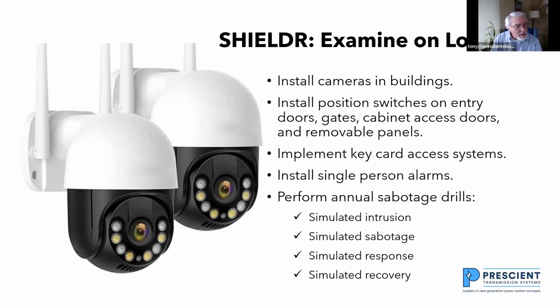And single person alarms, we shouldn't have single individuals able to access critical substations. What we should do is have it set up so that if 2 people aren't in a critical substation within 5 minutes of each other, security is alerted and security comes out to the site and asks a question. Why are you here? What are you doing? And then we should be performing annual sabotage drills where we simulate an intrusion, we simulate sabotage, we simulate response, and we simulate recovery. This would be an 8-hour drill at a specific substation. You do a different substation every year. And the assumption is that all groups that are going to participate through recovery get a chance to participate in these drills.